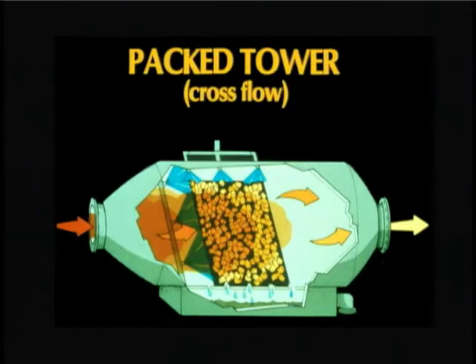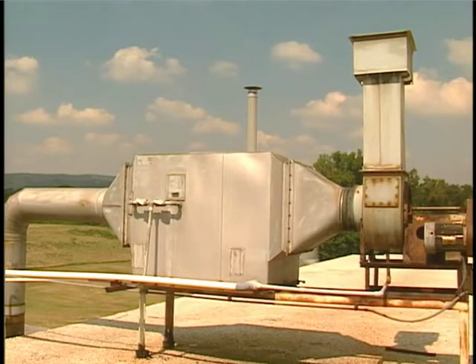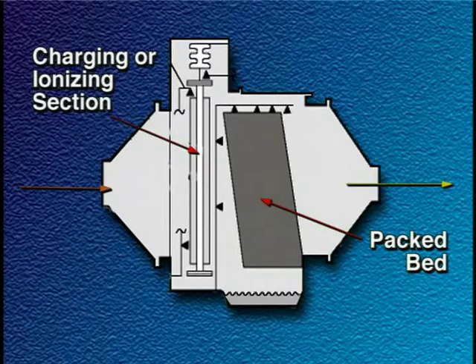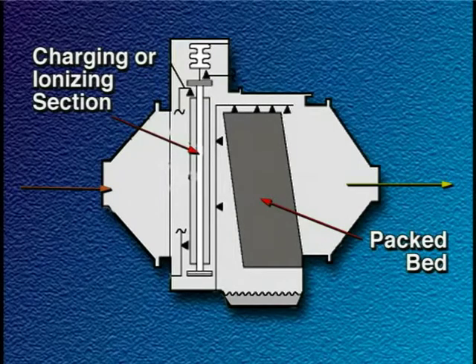In the cross flow scrubber, the gas stream flows horizontally through the packed bed, while the liquid flows down through the packing material. Because greater amounts of liquid can be used in this arrangement, the collector can handle high concentrations of solid particles without plugging. In some designs, the particles are charged before entering the packed bed in order to increase collection efficiency. These devices are referred to as ionizing wet scrubbers.